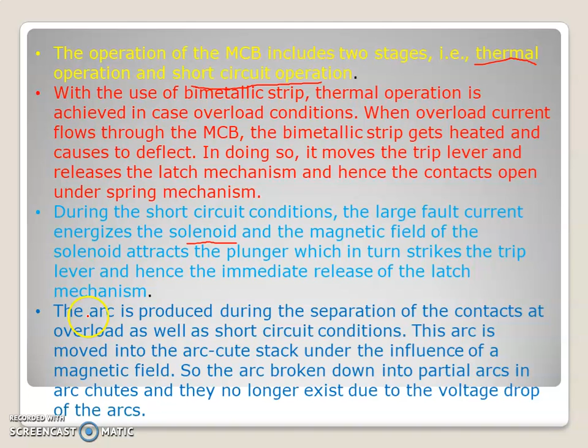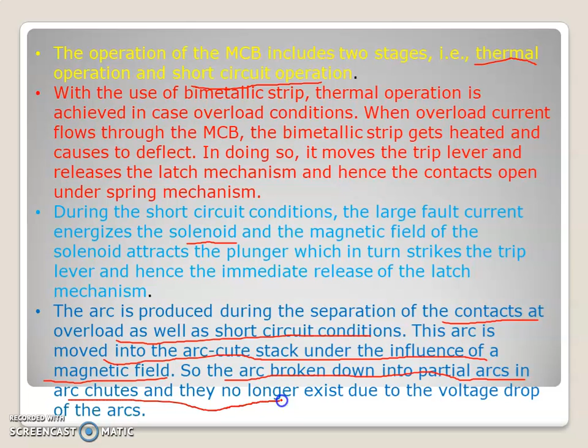The arc is produced during the separation of the two contacts, a moving and a fixed contact. During the overload and short circuit condition, this arc is moved into the arc chute chamber stack under the influence of a magnetic field. So the arc is broken into partial arcs in the arc chutes, and they no longer exist due to the voltage drop of the arc.